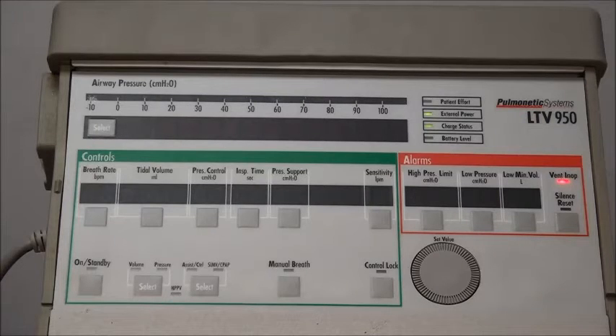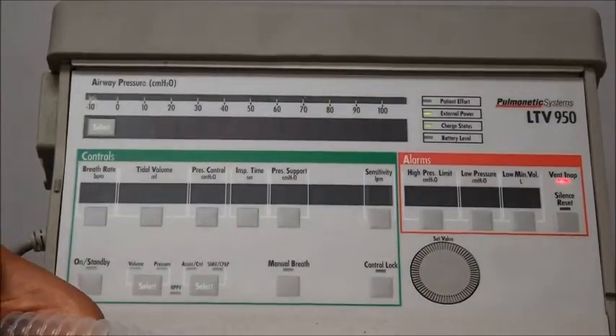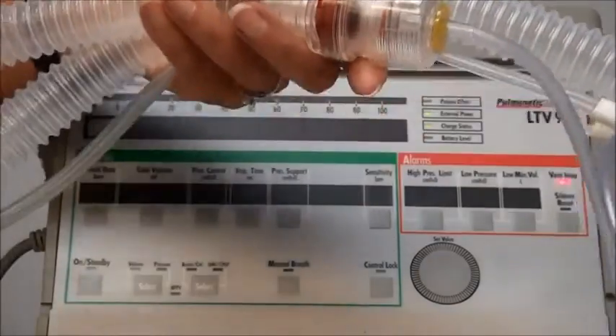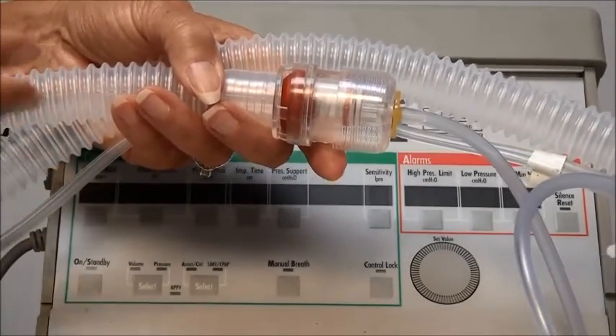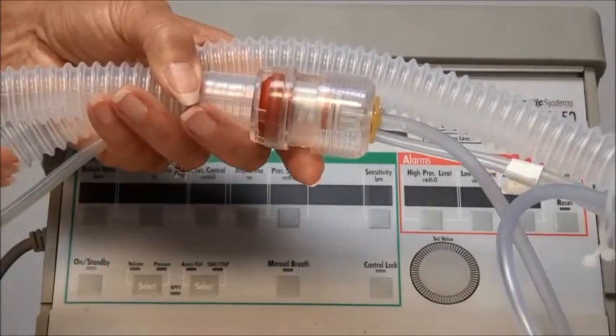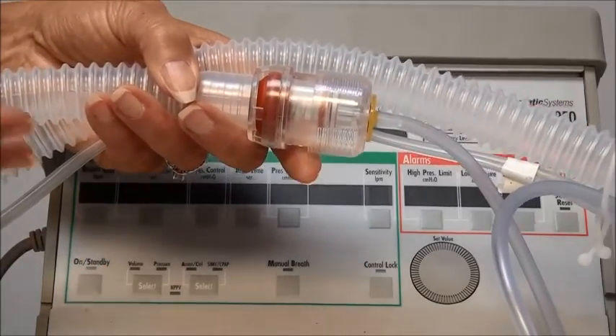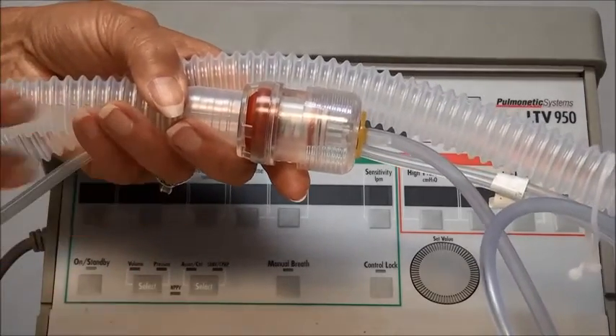Now, the low pressure alarm, that would be if the ventilator senses a pressure lower than what you'd have that alarm set at. And that could be any leak or disconnect. So if your patient comes off the ventilator, pops off the ventilator, or any of the lines on your tubing circuit come loose, or anything that you have in line that would have a leak or a disconnect or even a hole in your circuit. So if you have a low pressure alarm, again, that's not a problem with the ventilator, it's a problem with your circuit or your patient.